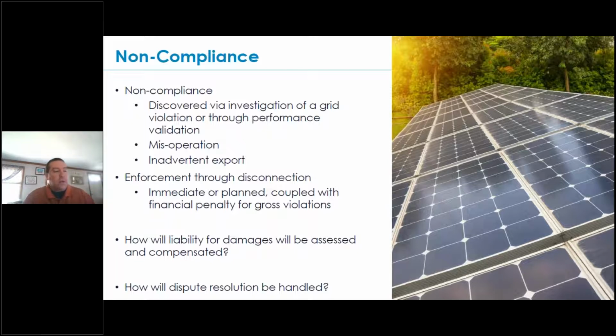We found the site was exporting higher than their ISA allowed. The good part was we found it in the wintertime, when load was a little lower, and we have different winter ratings, so the ratings are a bit higher. So it didn't damage the system or create an issue, but it would have during the summer period.